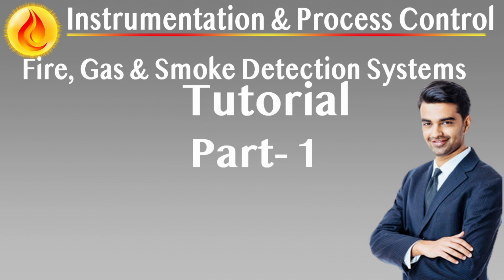Selection of point gas detectors, application criteria, detector preferences, and threshold design. Point gas detectors form the front line of local gas release detection. Their performance is defined by how effectively they detect gas concentrations at specific physical points, typically near potential leak sources, enclosed volumes, or air inlets. The selection of point detectors requires careful consideration of sensor technology, alarm thresholds, response latency, environmental resistance, and compatibility with the system's analog input architecture.